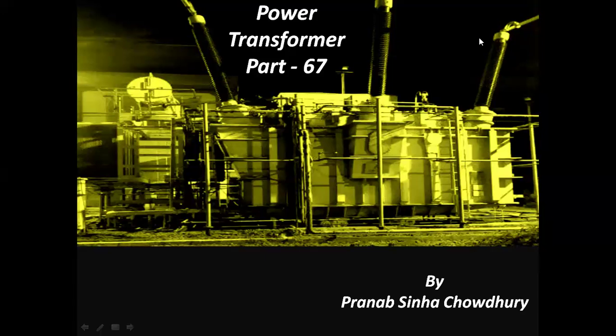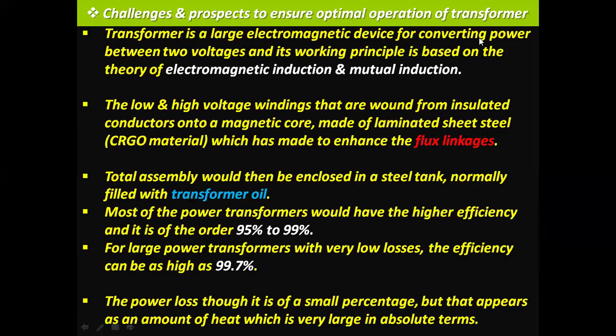Let's start with challenges and prospects to ensure optimal operation of transformer. Transformer is a large electromagnetic device for converting power between two voltages, and its working principle is based on the theory of electromagnetic induction and mutual induction. The low and high voltage windings are wound from insulated conductors onto a magnetic core made of laminated sheet steel, CRGO material, cold rolled grain oriented material, which is made to enhance the flux linkages.